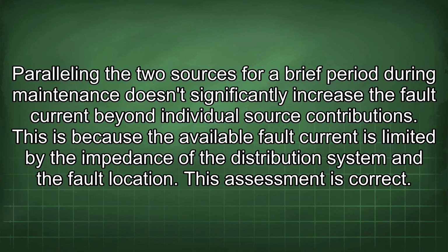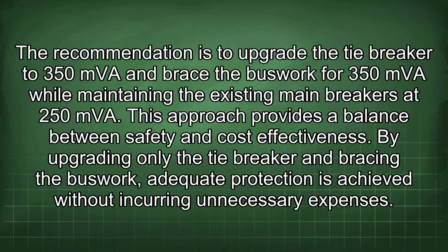This assessment is correct. The recommendation is to upgrade the tie breaker to 350 MVA and brace the buswork for 350 MVA while maintaining the existing main breakers at 250 MVA. This approach provides a balance between safety and cost effectiveness. By upgrading only the tie breaker and bracing the buswork, adequate protection is achieved without incurring unnecessary expenses.